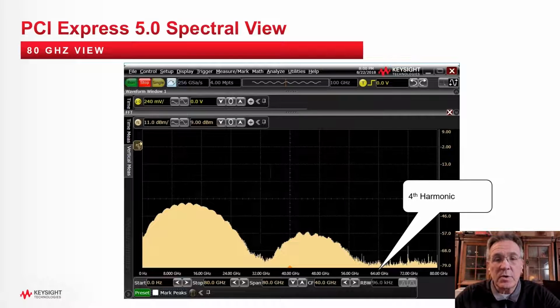So for testing purposes, the PCI SIG decided that a good minimum bandwidth for PCI Express technology testing would be 50 gigahertz. This becomes really important when calibrating the BERT output discussed previously, because that's where you expose the oscilloscope to the full bandwidth of the PCI Express spec operating at 32 gigabaud, and you'd see signals like this. So we specify a minimum bandwidth of 50 gigahertz, with a recommendation from Keysight of 59 gigahertz if that's within your budget.